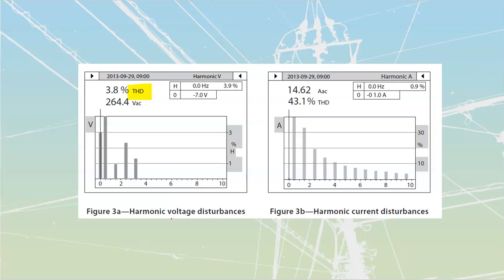and those spikes can tell you which areas you're really struggling with. Over here, we're seeing that the closer we are to our fundamental frequency, the higher the spikes are, and we're attenuating as we get further and further away. We should see roughly the same thing on our voltage as we get closer over here on our initial one. Then everything else past that is going to be dropping away a little bit further.